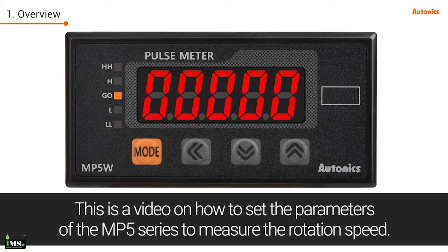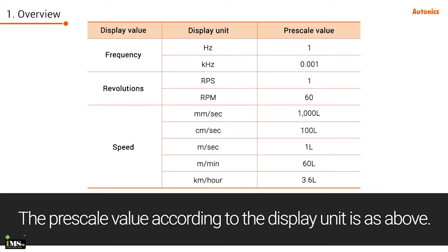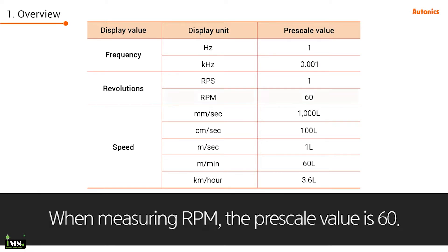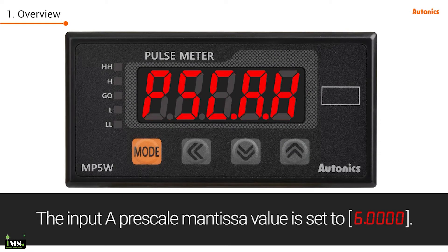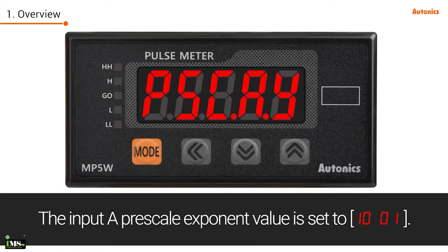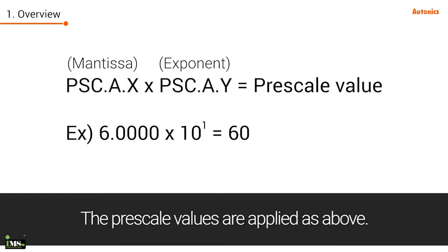This is a video on how to set the parameters of the MP5 series to measure rotation speed. The prescale value according to the display unit is as shown. When measuring RPM, the prescale value is 60. The input A prescale mantissa value is set to 6.0000, and the exponent value is set to 10 to the power of 1. The prescale values are applied as above.